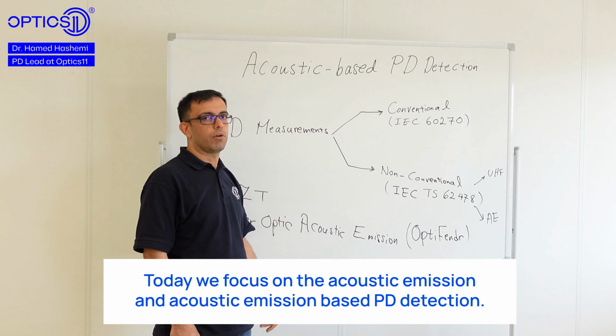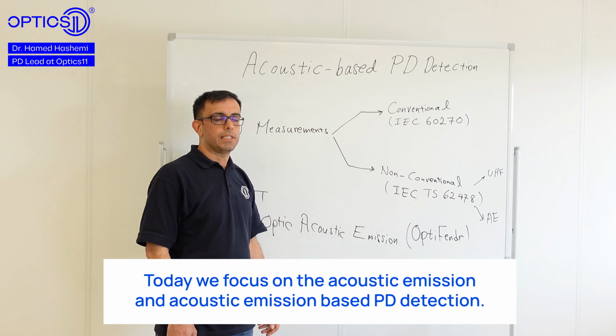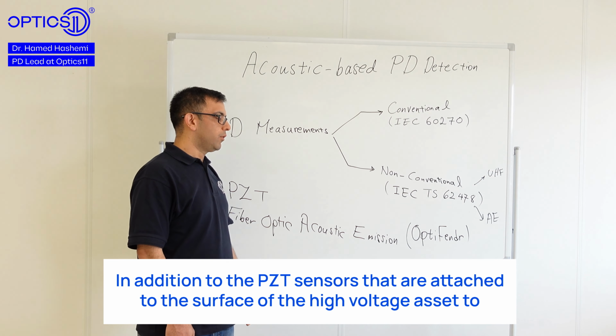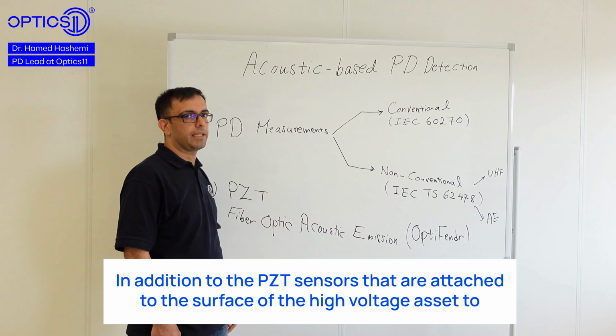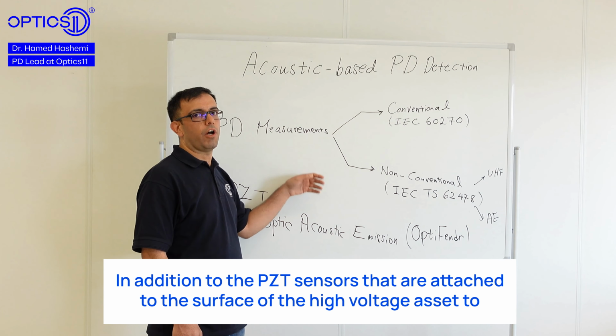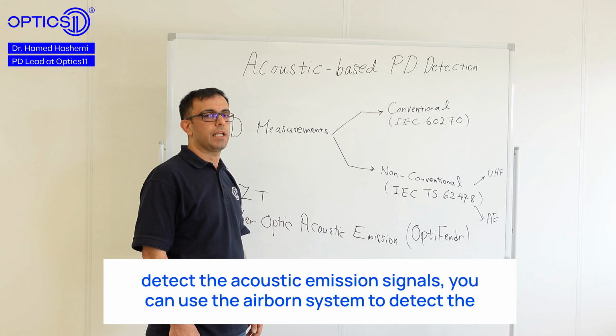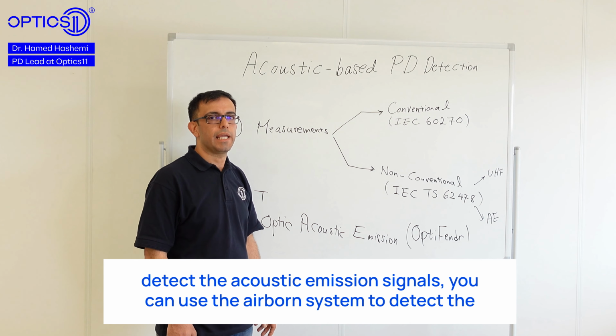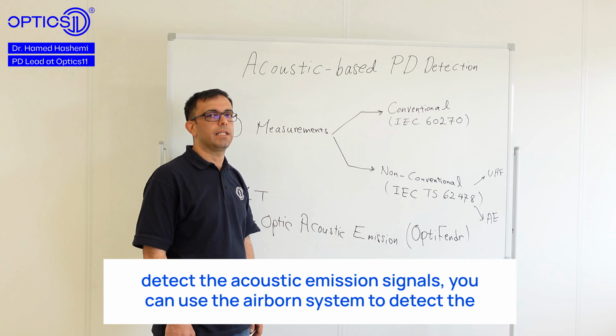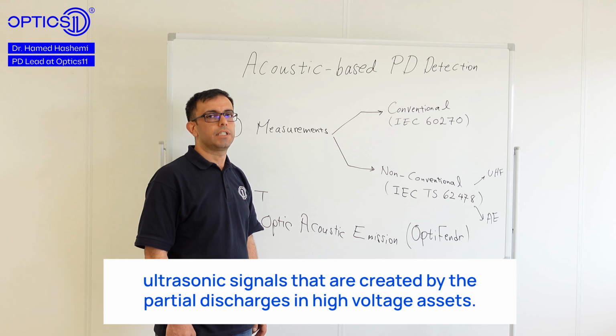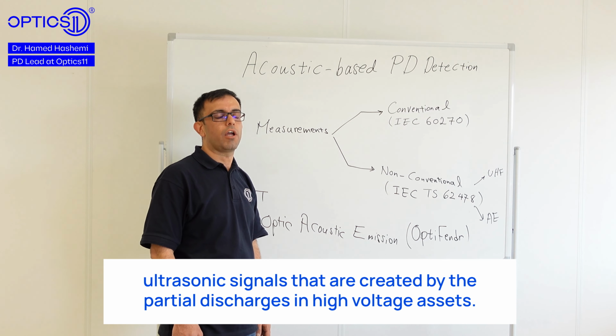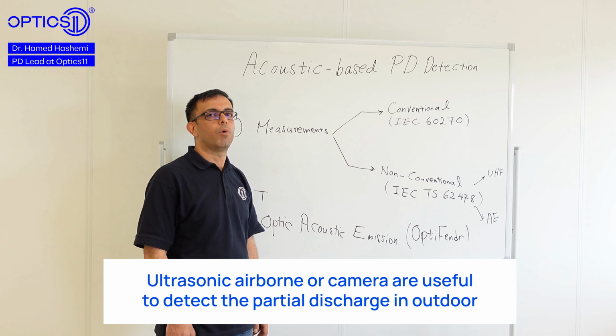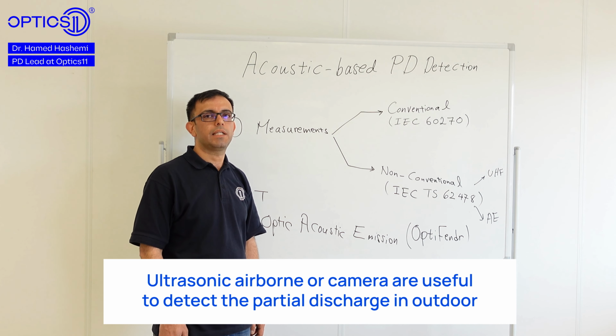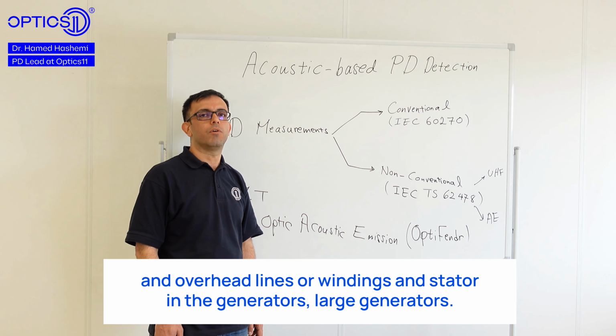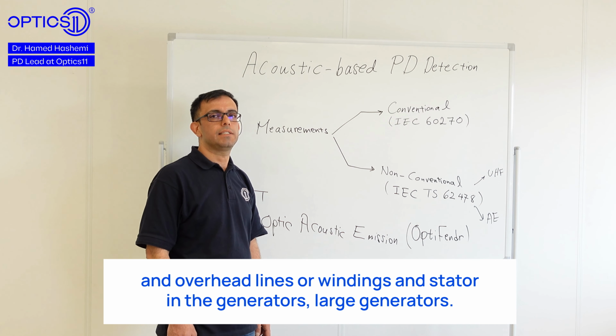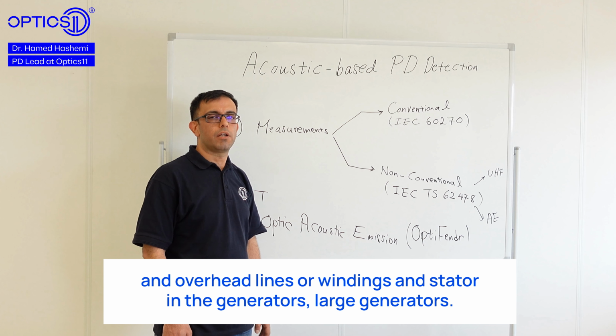Today we focus on the acoustic emission and acoustic emission based PD detection. In addition to the PZT sensors that are attached to the surface of the high voltage asset to detect the acoustic emission signals, you can use an airborne system to detect the ultrasonic signals that are created by the partial discharges in high voltage assets. Ultrasonic airborne detectors or cameras are useful to detect partial discharge in outdoor and overhead lines, or in windings and stators in large generators.